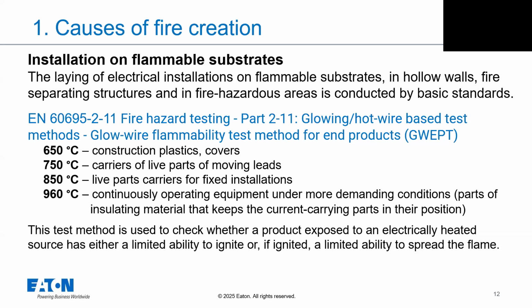We can take standard EN 60695 as the background of all product standards, which defines how the glow wire flammability test is done. Importantly, a testing temperature like 650 is only used for covers or construction plastic that isn't so important. But when higher temperatures are used, it's for parts which must carry the construction.